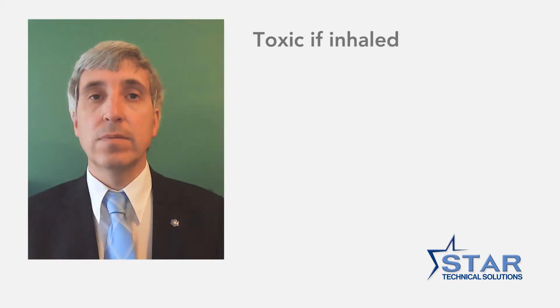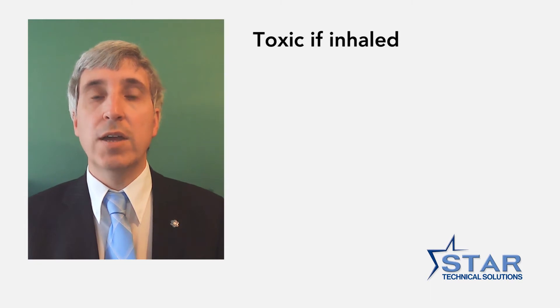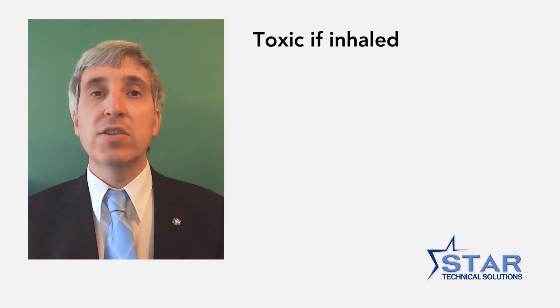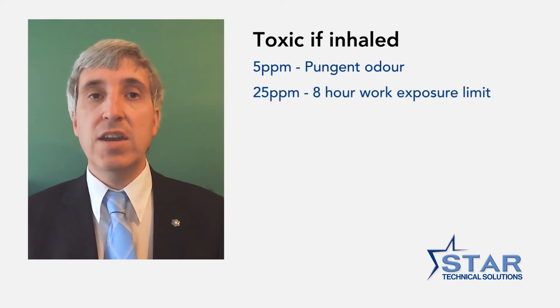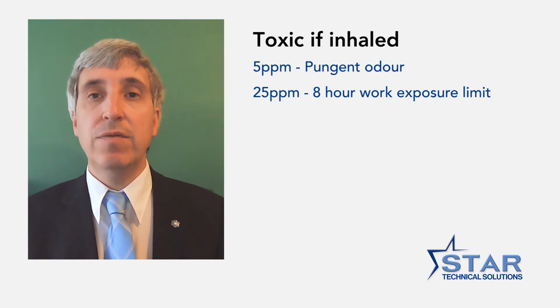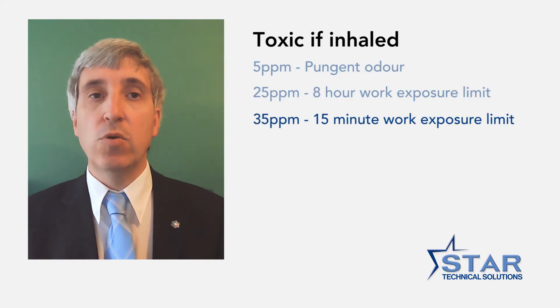First of all, we will look at the five hazards associated with ammonia. The first hazard is toxic if inhaled. Ammonia at concentrations as low as 5 ppm can be detected due to its pungent odour. The 8-hour work exposure limit is 25 ppm and its 15-minute workplace exposure limit is 35 ppm.